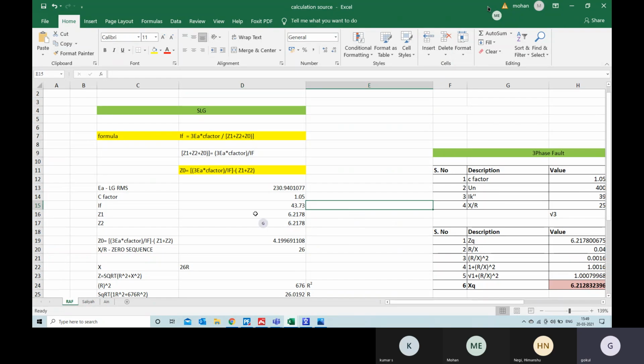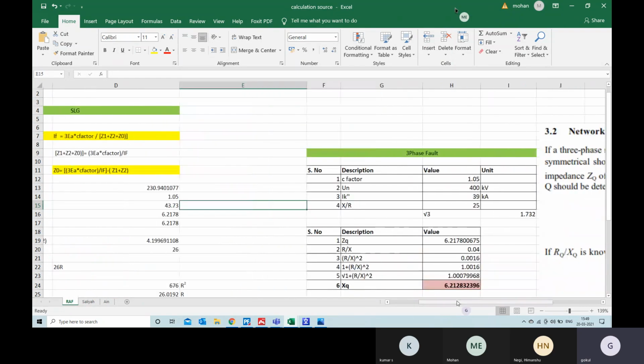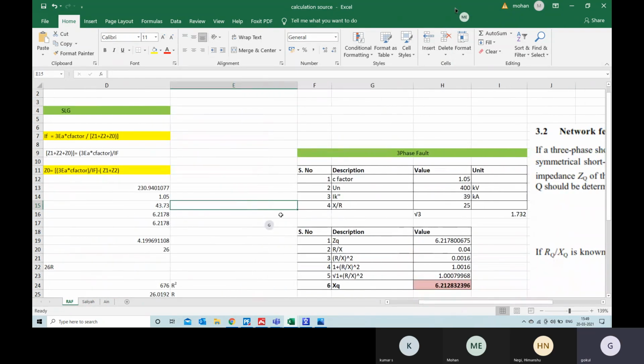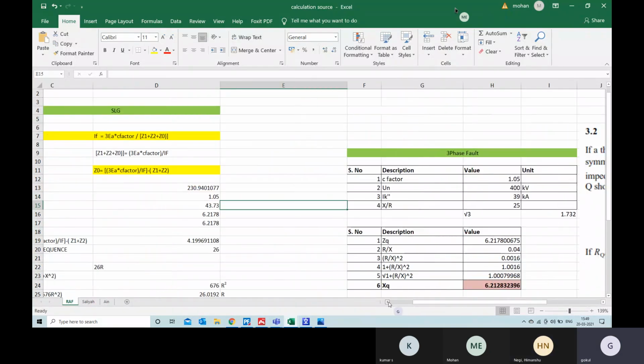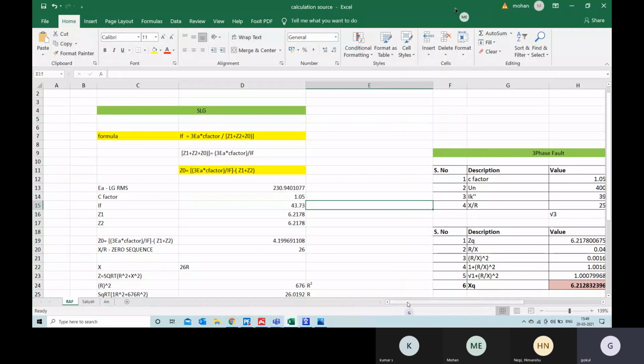And the impedance, you can take it from here itself, because this is the positive sequence, right? That's why I first went to three phase, then I went to single line to ground fault. We consider the same for negative sequence - for positive sequence and negative sequence they are the same. So that's what I have considered.